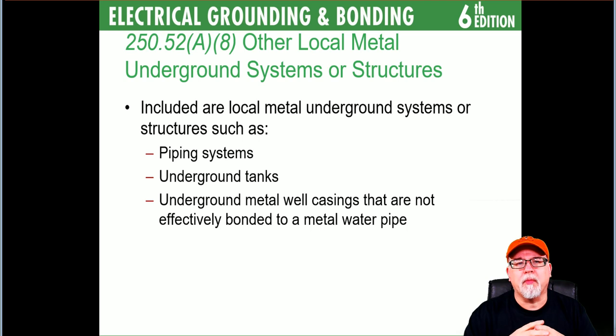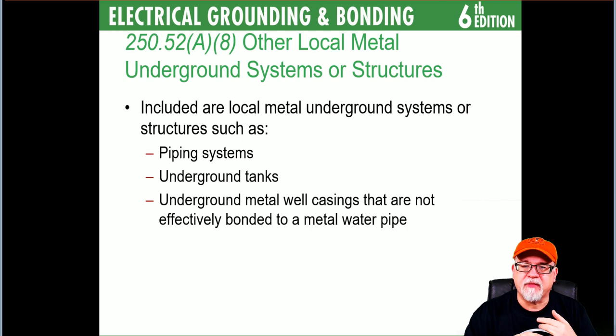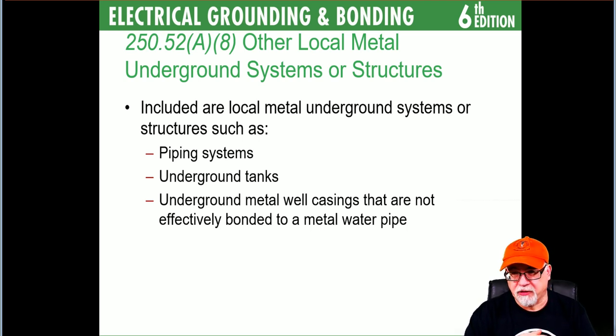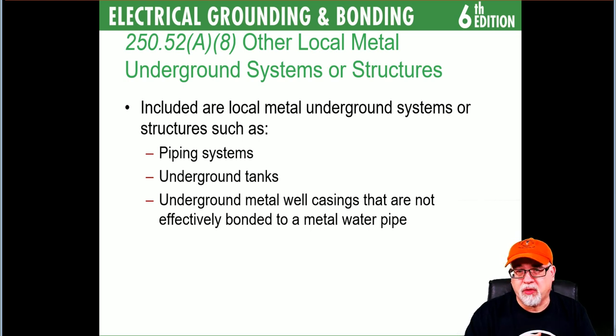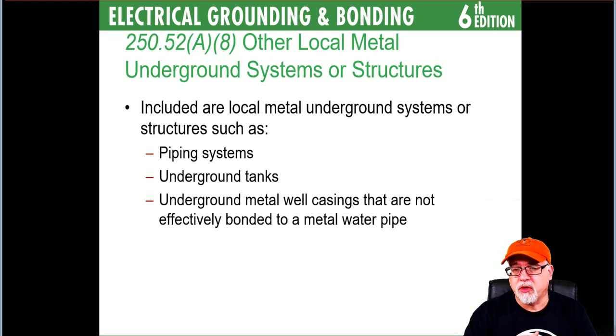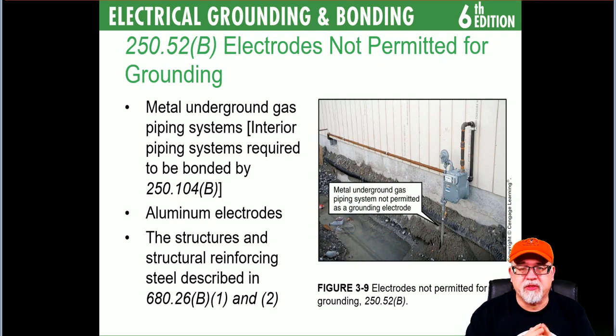250.52(A)(8) — other local metal underground systems or structures. Included are things like existing metal piping systems in contact with the earth, underground tanks, and underground metal well casings not effectively bonded to the metal water pipe. It's all about surface area. I usually don't see a lot of these on new construction sites. Well casings are usually so far away it makes it moot to be part of the grounding electrode system — you'd need to confirm with your jurisdiction what they expect.